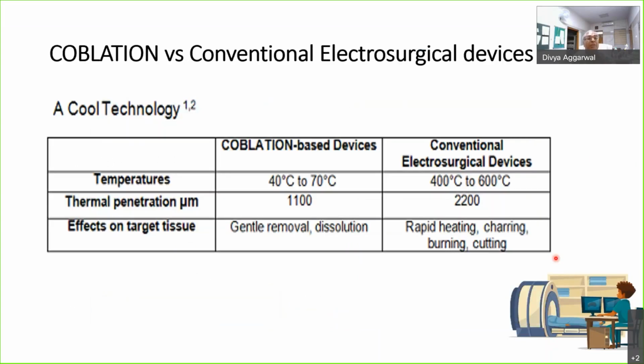So what is the advantage of COBLATION over a conventional electrosurgical device? Temperature, as I said, is 40 to 70 degrees, and in conventional it is 400 to 600. It may go up to 700 or more. Thermal penetration is much less as compared to conventional, it is 2200, whereas here it is 1100 micrometer. And what is the effect on the target tissue? There is a gentle removal and dissolution, whereas in a conventional electrosurgical device, there will be rapid heating, charring, collateral damage, burning, and cutting.